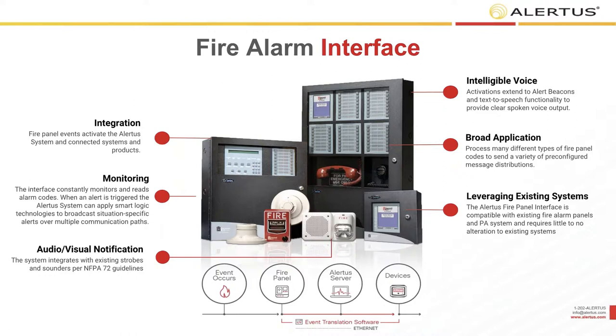For audio-visual notification, we can use the strobes if labeled appropriately — either labeled 'Alert' or with no label — or supplement with all the Alertus endpoints. For audio, we can leverage your speakers, which are designed by the building engineer to be audible and intelligible to relevant standards, and inject an audio message into your speaker system to notify the entire building. The interoperability is broad: Honeywell, Siemens, Tyco EST — even if you have different brands across your network, we can use the same technology to unify messaging from those panels across your campus.